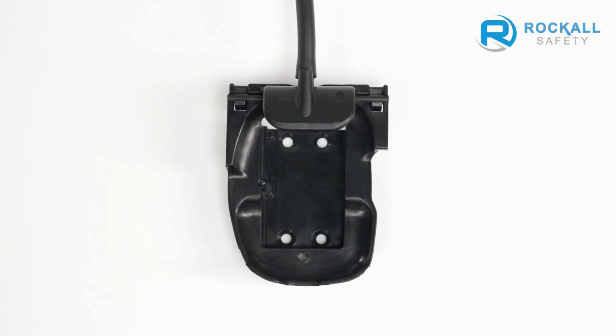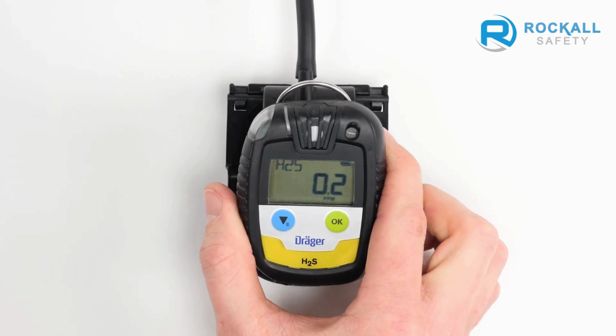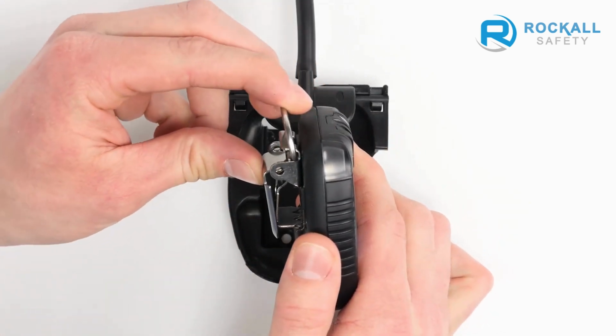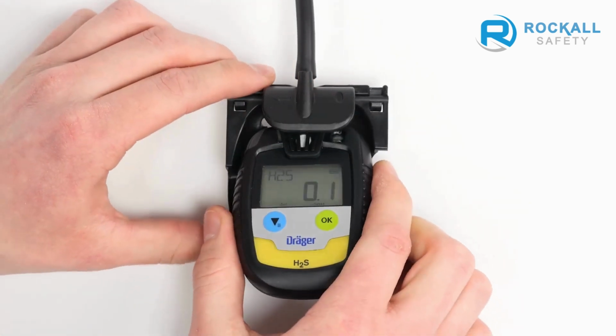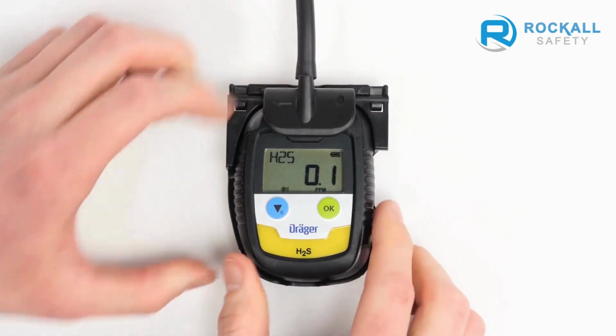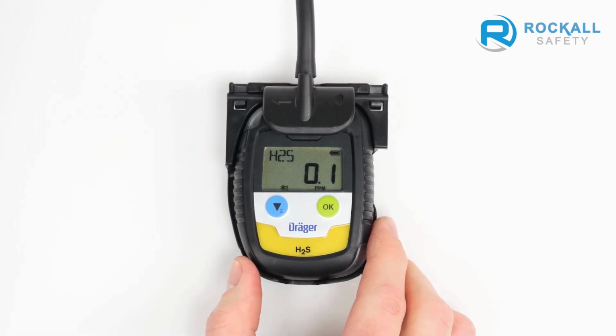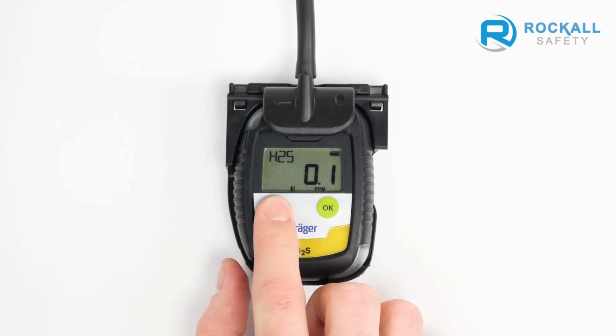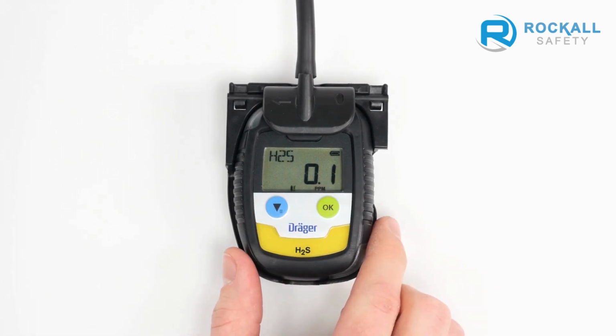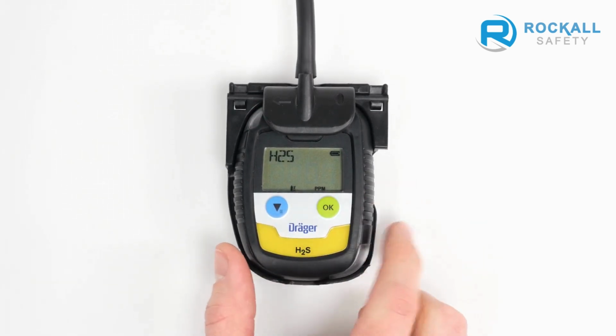The sensitivity calibration serves to calibrate the sensors to a preset gas concentration. Raise the clip on the pack, attach the calibration adapter, and connect it to the test gas cylinder. In order to carry out a sensitivity calibration, press the menu button to enter the menu. The icon for span calibration will start flashing. Confirm with OK in order to start the sensitivity calibration.